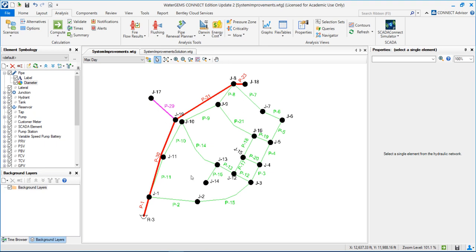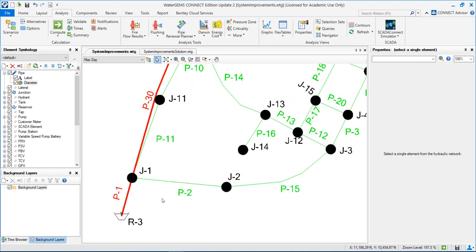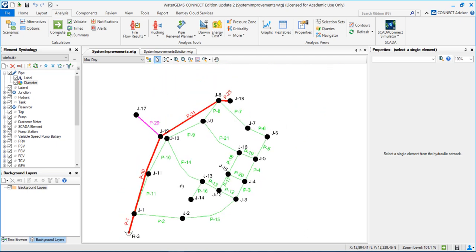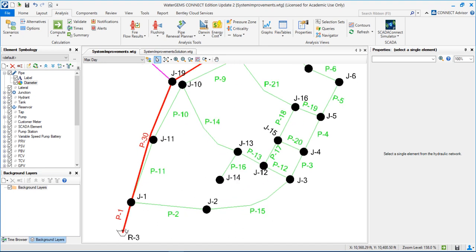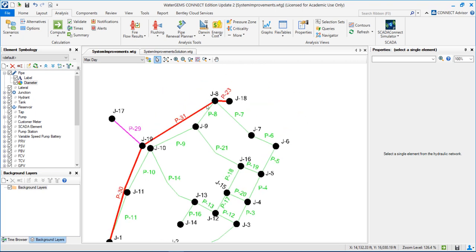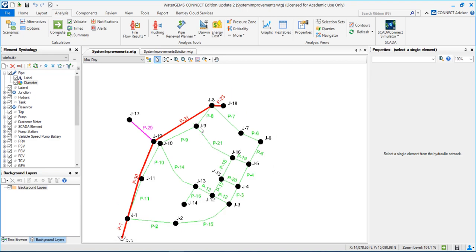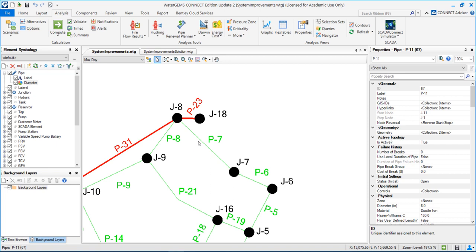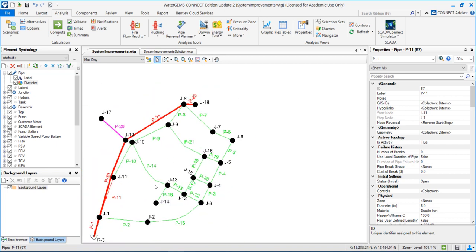Check if our conditions are met — velocities or pressures. If they are not met, we need to increase the pipe diameter more and more. If they are already met, we move to the downstream pipe. Here two approaches can be used: we can start by sizing and upsizing pipe P2, connected to J1, and then moving downstream. Another way is to induce the main flow along the red line entering J8 into P7 or P8, so we can start by upsizing P8 or P7 and then moving downstream.